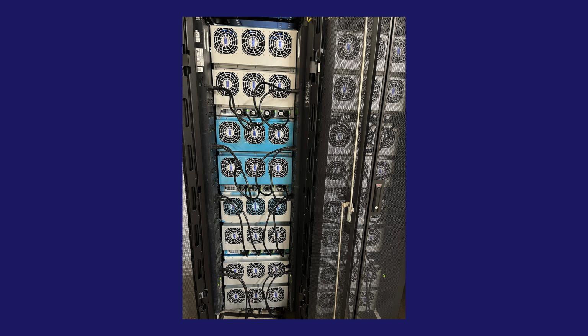They pulled about 4.5 kilowatts each. We gave each of them about 6.5 kilowatts of available power. In a rack, and ultimately in the facility, what we would do is put 4 of those 10U servers, or say we were using 7U servers, we'd still only put 4 into the rack, and then we'd blank all of the empty spaces in the rack to contain air, making sure hot air goes into one aisle and cold air goes into another aisle.